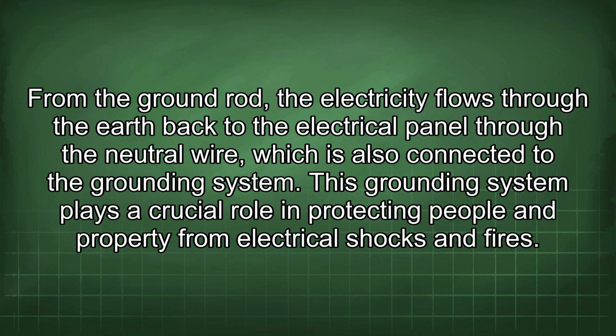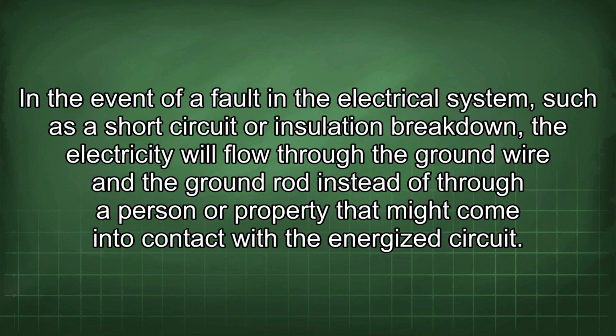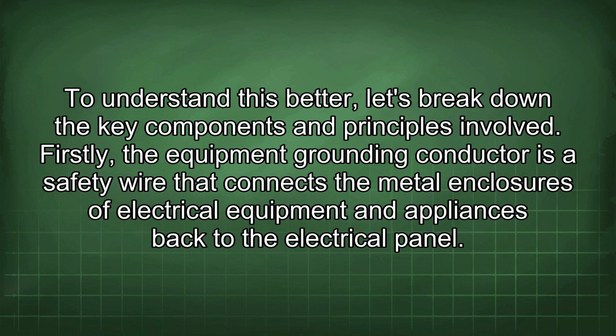This grounding system plays a crucial role in protecting people and property from electrical shocks and fires. In the event of a fault in the electrical system, such as a short circuit or insulation breakdown, the electricity will flow through the ground wire and the ground rod instead of through a person or property that might come into contact with the energized circuit. To understand this better, let's break down the key components and principles involved.